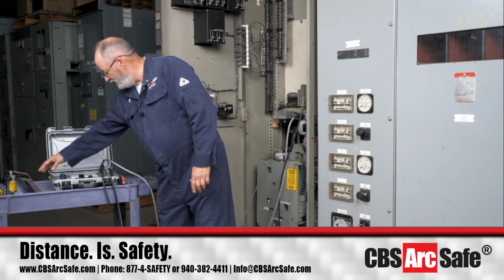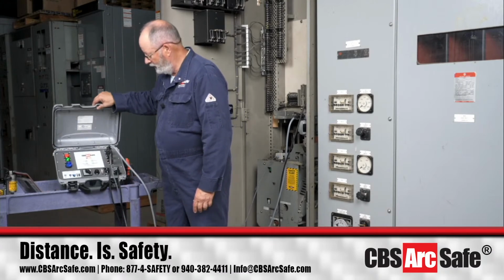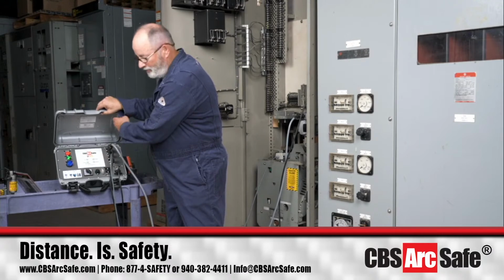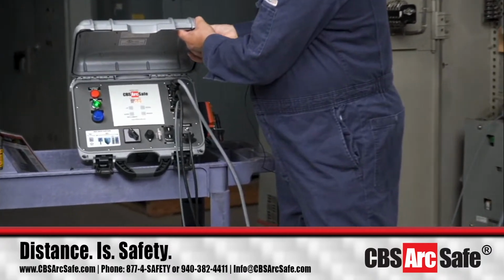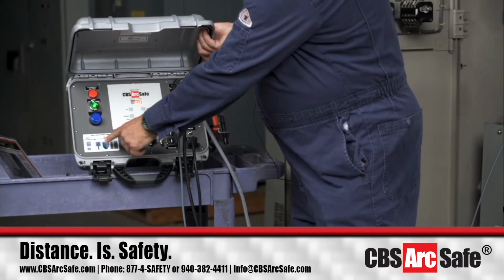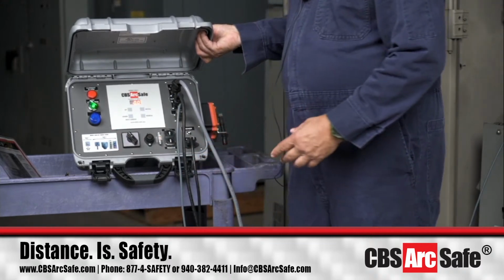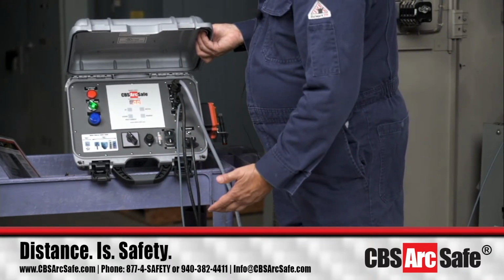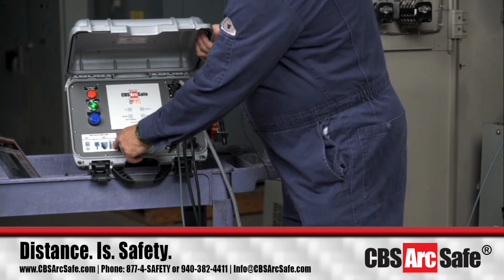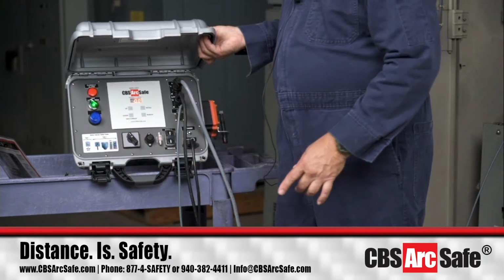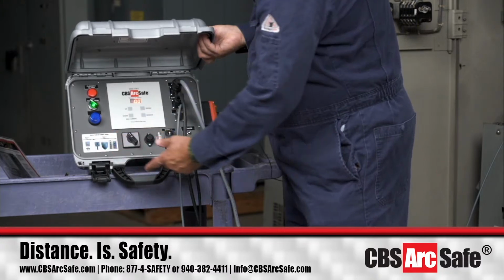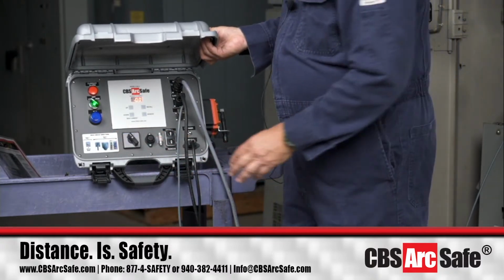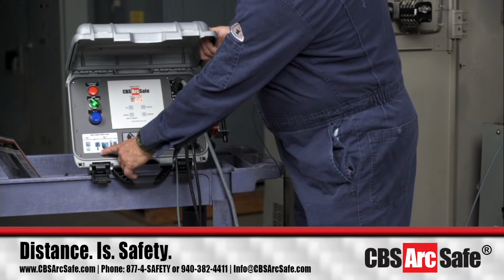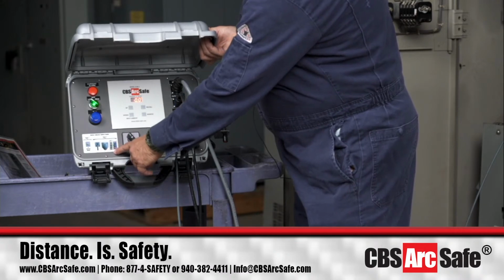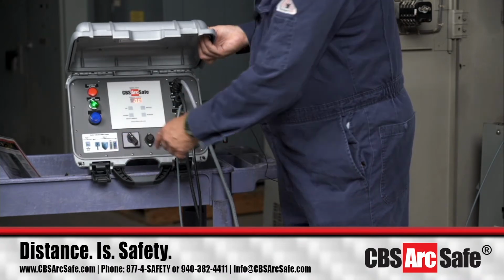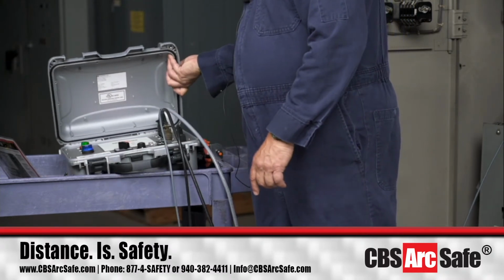Now if you look at the display here, Brian, zoom into this part please. We have type 1 and type 2, and this is how we know which type of cubicle we need to operate. If we're operating type 1, where we just use the supervisor link, we leave it in type 1. If we have the breaker control switch, the knob switch, or what looks like the big molded case breaker switch, then we put it to type 2.